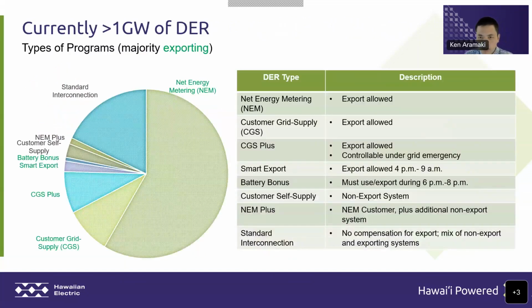This next slide just shows a breakdown of the DER that we have on the system. I mentioned we have over 1 gigawatt of DER across the islands. This shows that around 75%, which are the green ones, are generally exporting systems. The remaining 25% or so either do not get compensated for export, but also have the ability to export, or are not allowed to export at all.